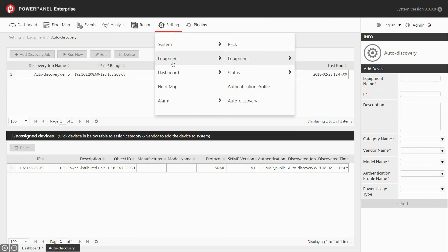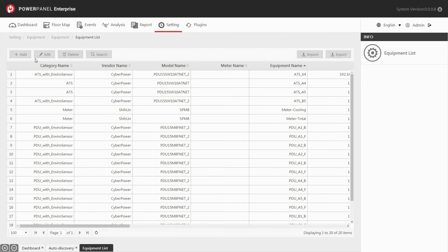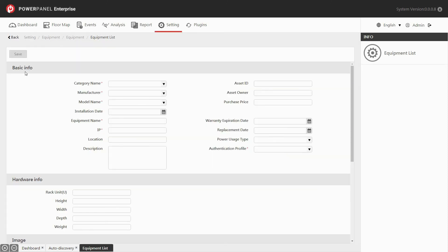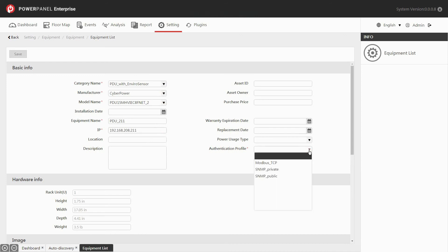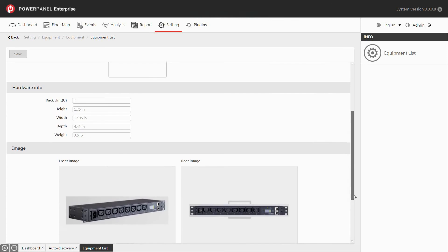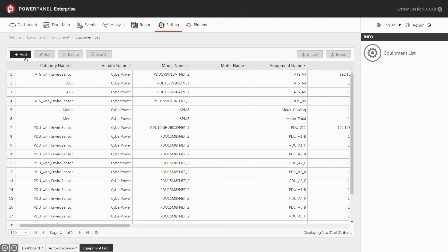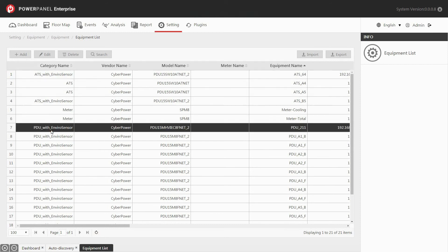The equipment list allows you to add new equipment or maintain equipment information. Go to the setting drop-down menu and under equipment, select equipment list. Click on the add button to add new equipment. In the basic info section, select the category name, manufacturer, and model name from the drop-down list built in by the system. Name the equipment and enter its IP address. Select the authentication profile to apply a community name to the equipment. You can scroll down to see the information and images of the equipment. Click save. You can see the new equipment has been added to your list successfully, and the equipment list setting is complete.